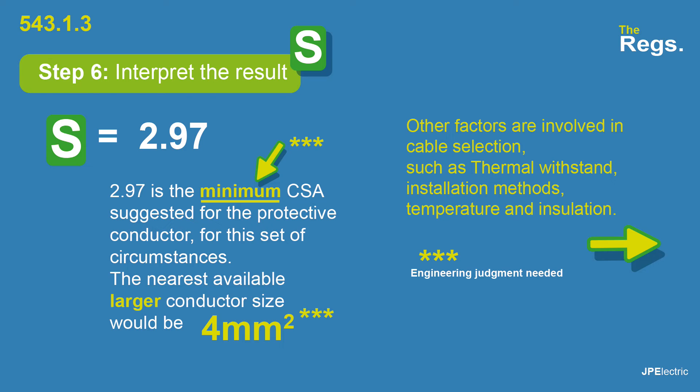There are other factors involved in cable selection: your thermal withstand, installation method, temperature, insulation, and length of run. The adiabatic equation can give you quite surprisingly small sizes of protective conductor, so you use your engineering judgment to see if the suggested size is suitable.